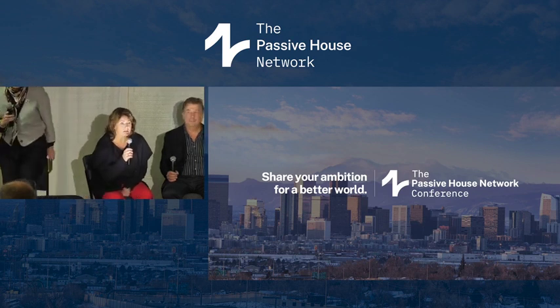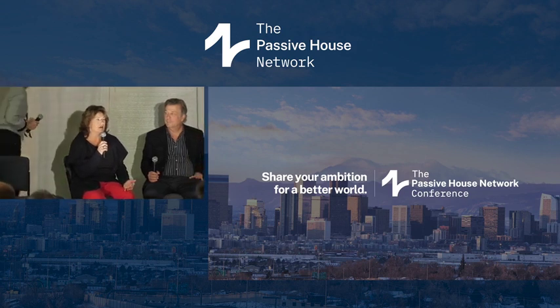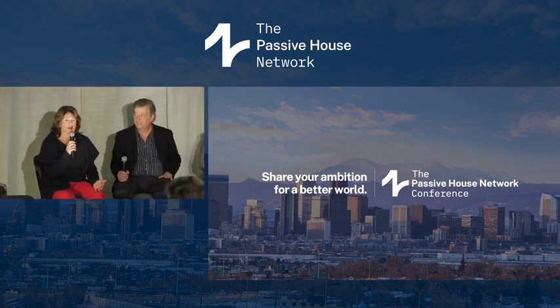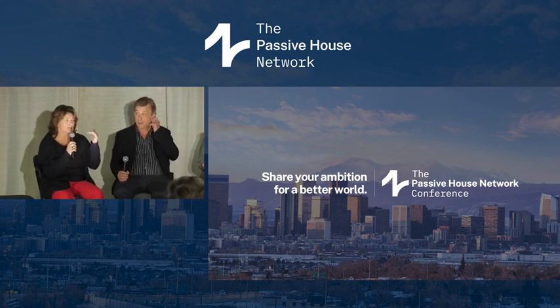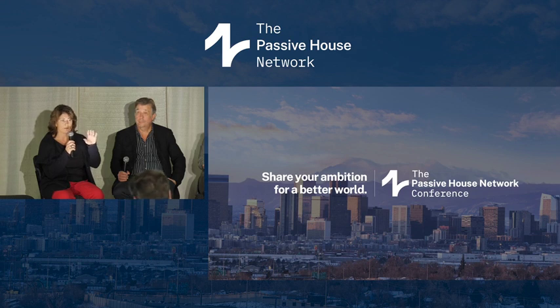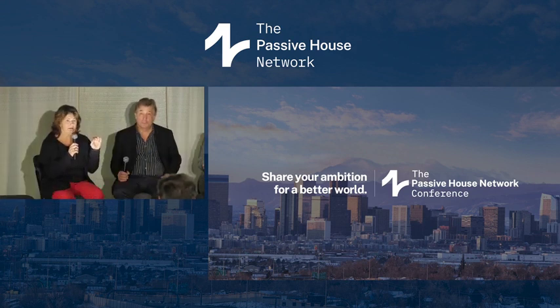I would, especially from an embodied carbon standpoint, sorry if Mitsubishi is in the room, not go with VRF. If we wanted to use heat pumps and do central heating, I'd go with a hydronic system where the heat pump, either geothermal or air source, feeds the rest of the building. This reduces the chance for leaks and harm to occupants, and it's just a more elegant solution. On the other hand, high performance individual cold climate PTACs, the little heat pumps that go through the wall, afford unbelievable cost savings to owners, in the millions of dollars depending on building size, and give individual control when they want it.